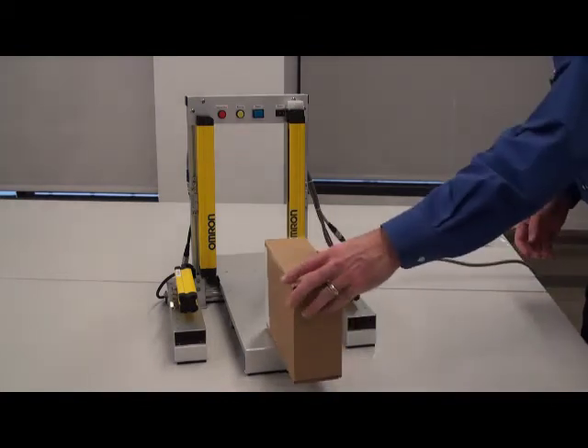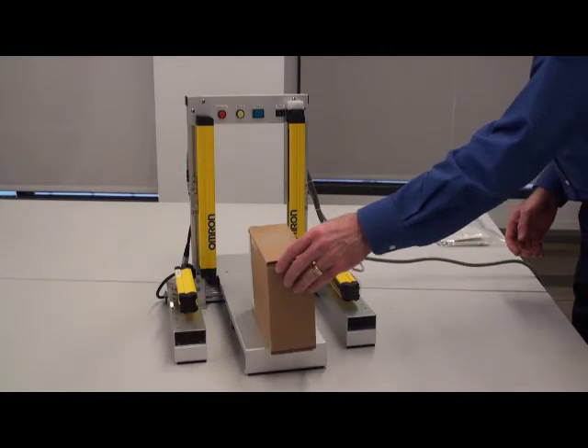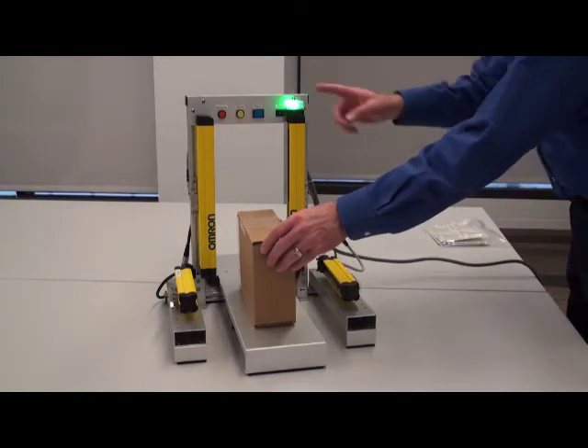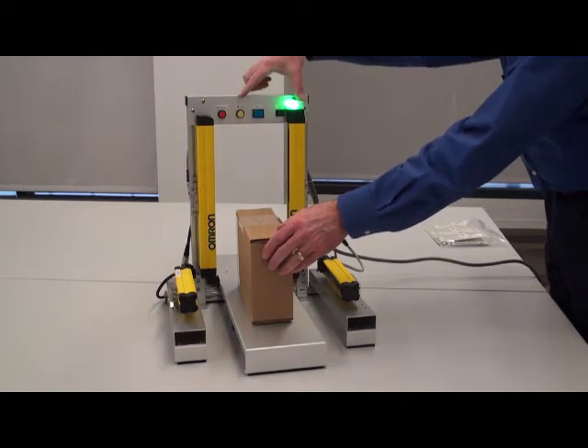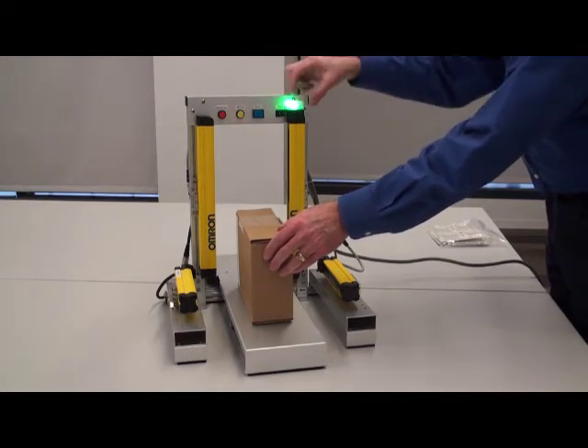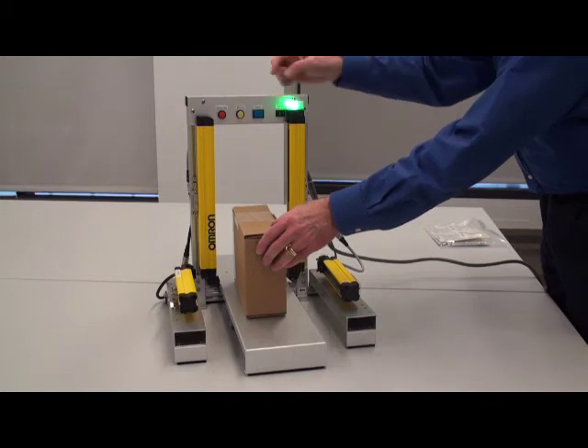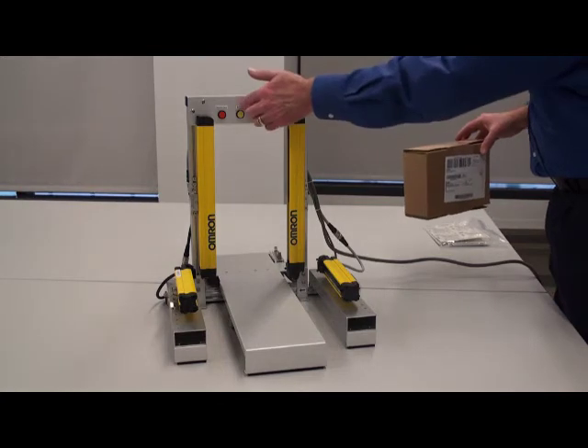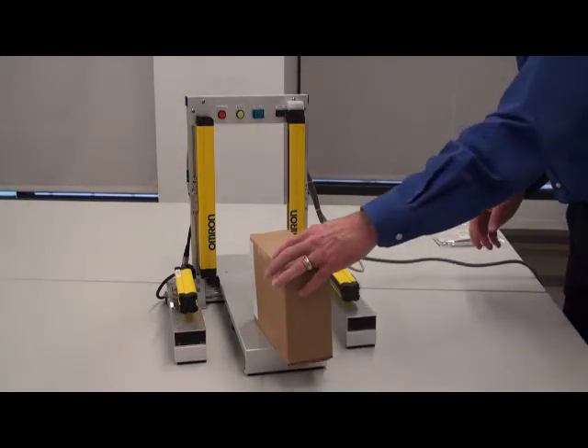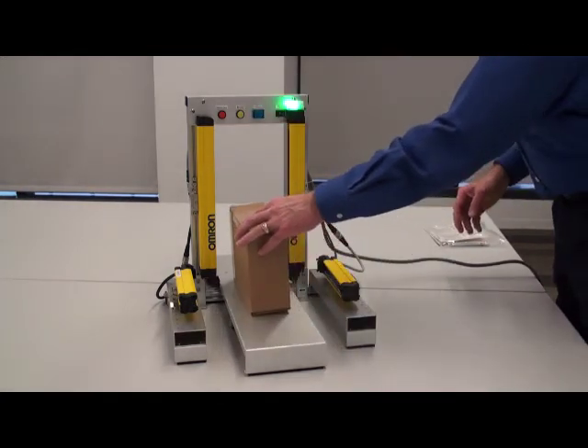Here is like a box coming through. And it's going slowly through. And now you can see that we have two muting indicators. The one on the panel and the one on the light curtain. The reason we have two here is because sometimes not everybody is going to want to use the muting lamp on the receiver of our light curtain. They might just have a muting lamp in the panel. So again, we go through. There's your muting.